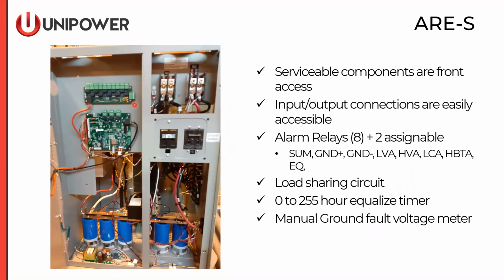We have the ground fault meter available via the front panel display, also displaying the severity of the ground fault in either ohms or voltage. Looking at the open door of this charger, you see that most user serviceable components are easily accessed. There's plenty of room in these cabinets to access the components that might require replacement, to include all the PC boards, DC and AC breaker on the front mounting plate, as well as capacitors that might need to be replaced every 15, 20 years. Nowadays, capacitors are lasting a good long time. Again, all relays, just like with the ARE-M, and alarms, we can assign a programmable delay. Equalize timer is always present. Next slide, please.